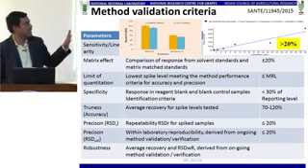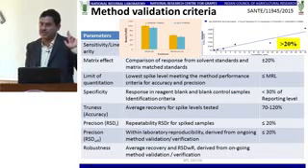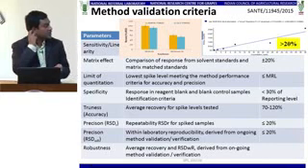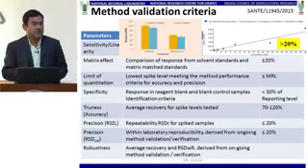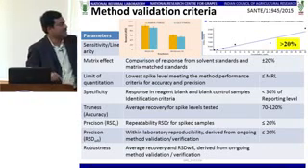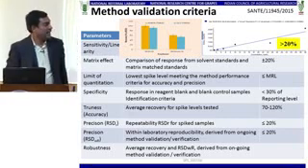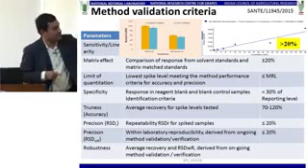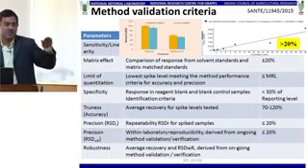So these are the major things. First thing is sensitivity or linearity. The minimum check requirement is 5 levels of linearity check, and if it is more than that, 6 levels is further good. So what you do here, you get such a linear graph. When you look at any linear graph, you see that each and every point is not on the straight line, because a straight line is something which is a trend line drawn across all these points. And here there is a definition that the deviation of a point from the straight line should not be more than 20%. That should be within 20%.